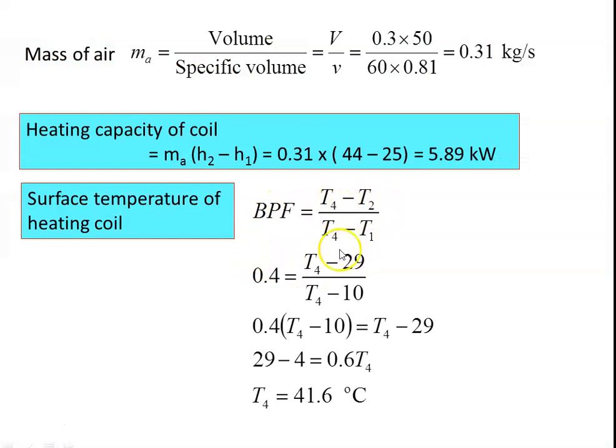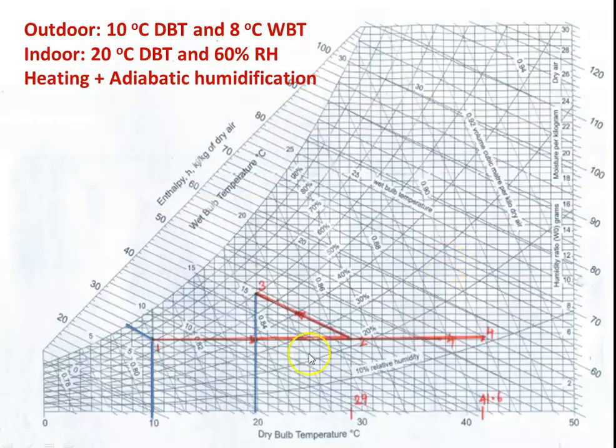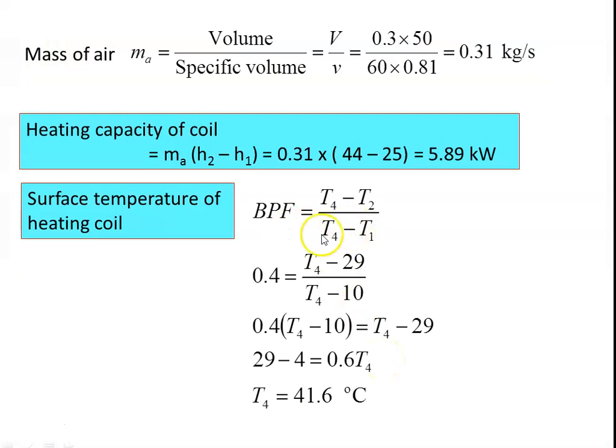The bypass factor equation is: BF = (T4 − T2) / (T4 − T1), where T4 is the surface temperature of the heating coil, T2 is the outlet temperature, and T1 is the inlet temperature. Bypass factor = 0.4, T2 = 29°C (from chart), T1 = 10°C (given). Rearranging and calculating: T4 = 41.6°C. That is the surface temperature of the heating coil.